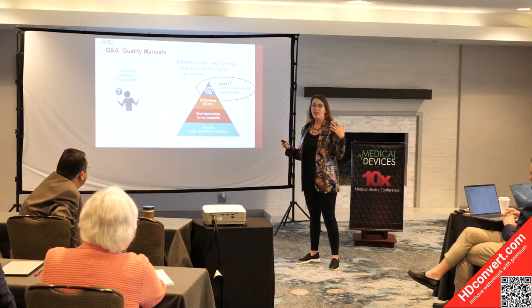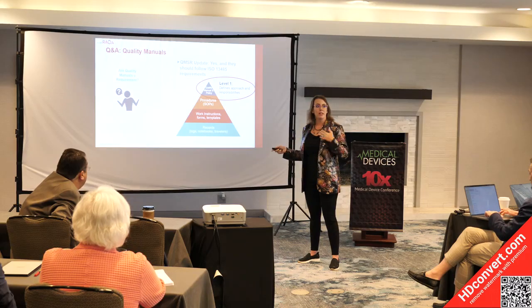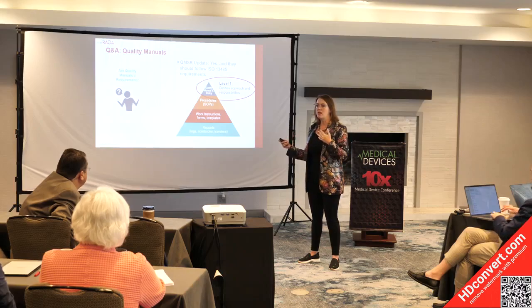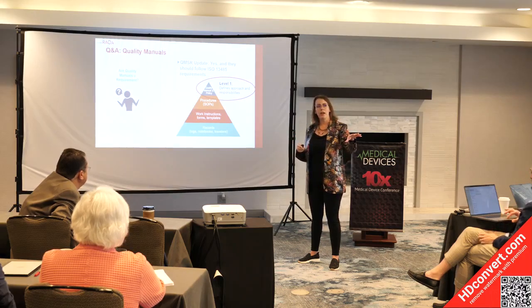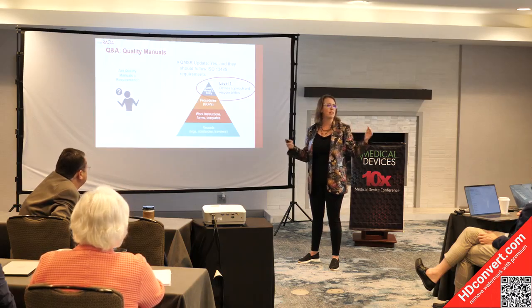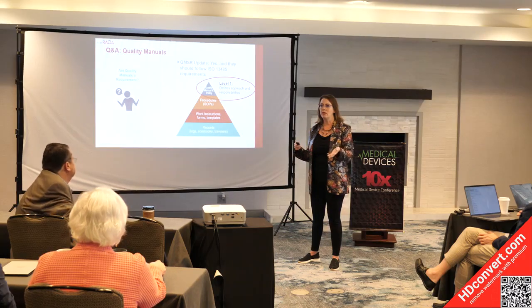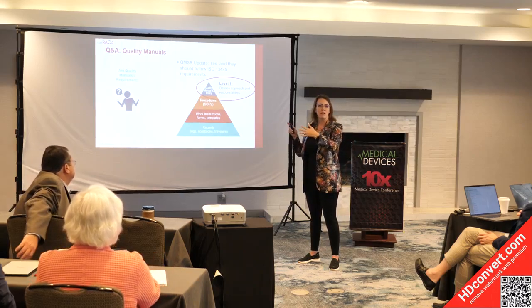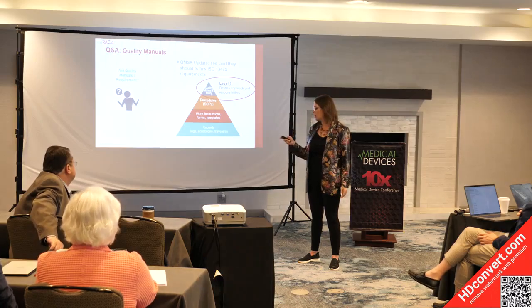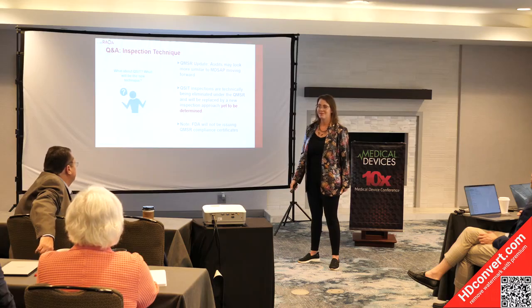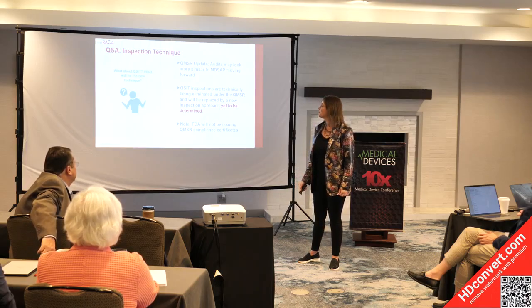A number of procedures like quality manuals that are technically not a requirement under the QSR will now be required under the QMSR. If you already have ISO 13485 certification, it may not be a big deal. But if you don't — if your quality system only complies with the QSR — there will be differences that are a bigger deal. Notably, at my last FDA inspection, the inspector asked for quality manuals even though it was an FDA inspection, not an ISO audit — so they're asking for that already.